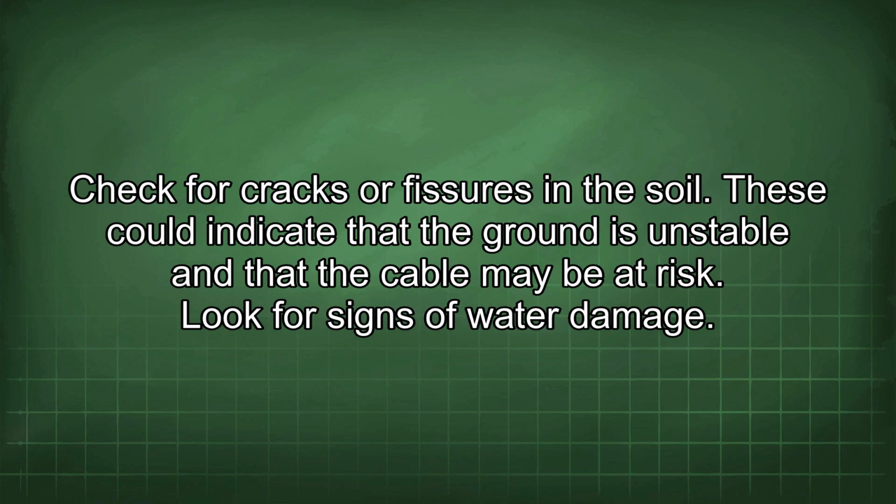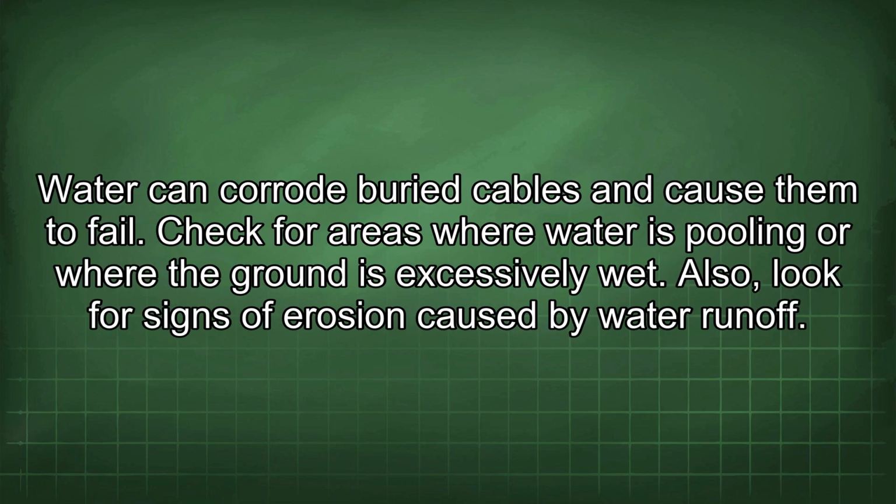Look for signs of water damage. Water can corrode buried cables and cause them to fail. Check for areas where water is pooling or where the ground is excessively wet. Also, look for signs of erosion caused by water runoff.